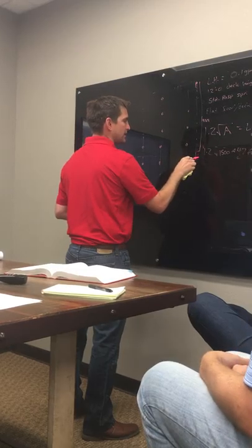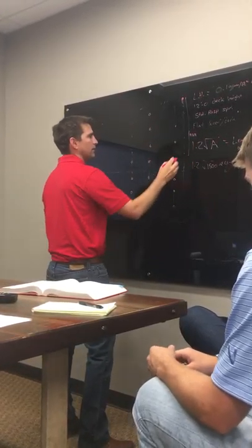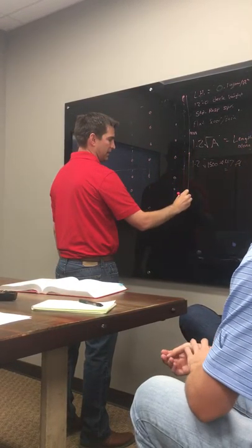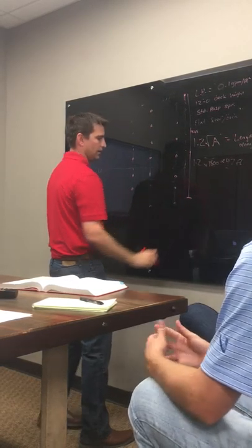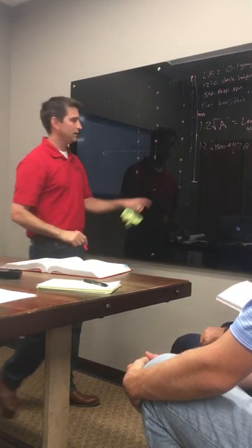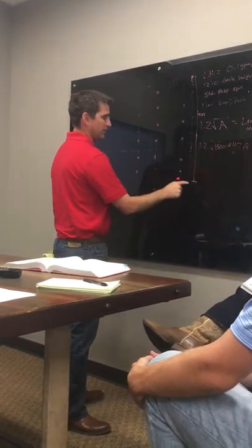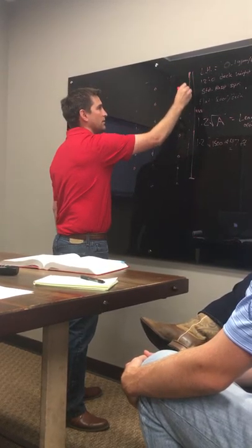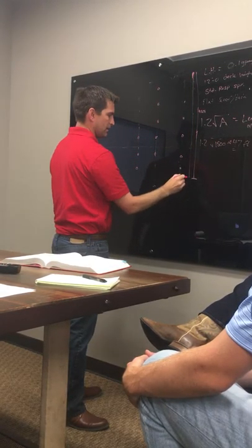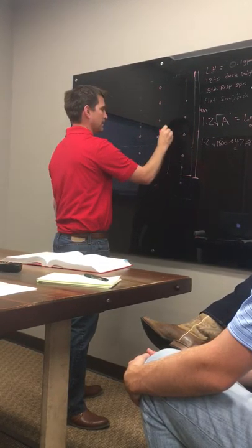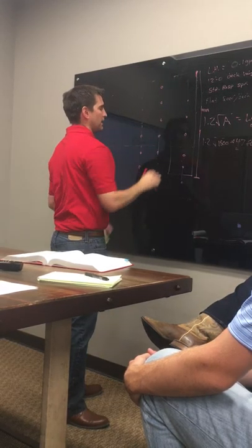Okay, so let's say I had this same situation, but my 47 feet put me down to here. I'll trick you a little bit. Follow exactly what I told you, you won't be tricked. Same thing, my main's right through the middle. The 47 foot puts me here, so I'm gonna do my remote area. I'm gonna come down here, cut across halfway, and come back up.